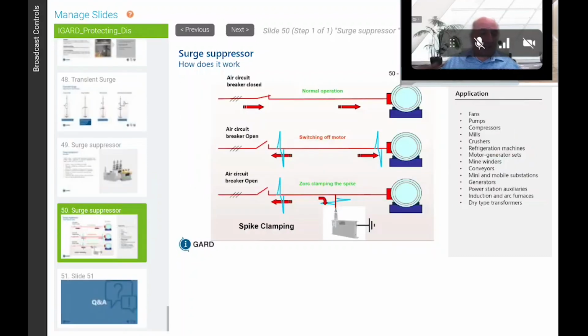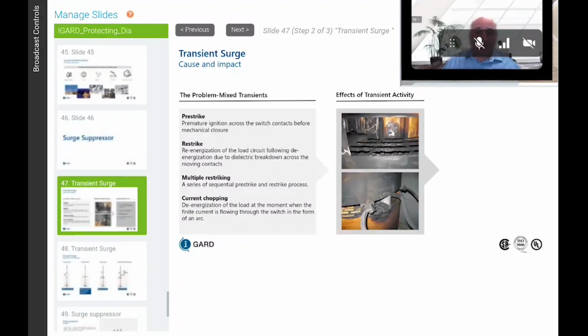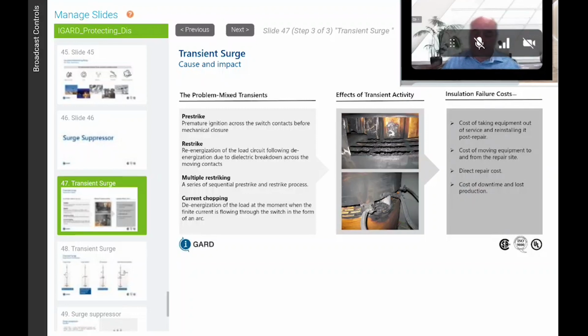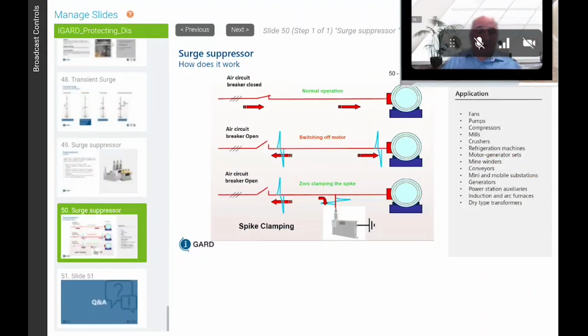And we look at different types of surges. These are some of the surges that we look at. In normal operation, when you switch the circuit breaker on or off, you have traveling waves that can multiply when they hit a reflective point and come back to cause this kind of damage. What we're trying to do is minimize this damage that occurs on a transformer or a generator. So the surge gets shorted to ground, and we protect the system that way. Spike clamping is a beautiful thing. Fans, pumps, compressors, mills, all these things we can protect with a surge suppressor. But more importantly, I'm working on a job now where some external capacitor switching can cause a surge in the line, so we would shunt the surge to ground.